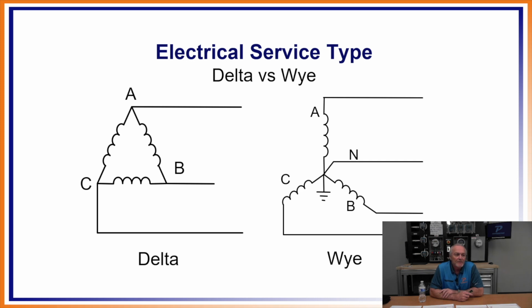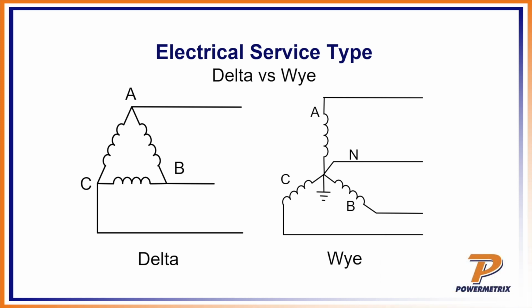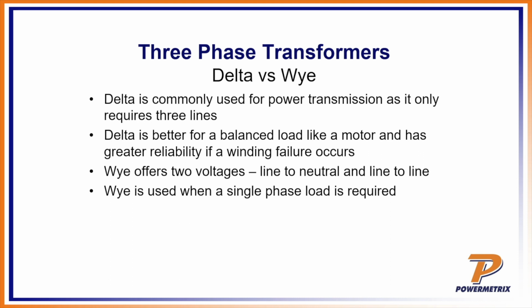So the two electrical service types that we talk about all the time are delta versus the Y, right? So delta, you'll hear guys say it's pretty easy to recognize the delta, because it's shaped like a delta, and then the Y is shaped like a Y. And you probably recognize the one on the right from Back to the Future. It looks a lot like that flux capacitor, doesn't it? The one on the right there. So 3-phase transformers, delta versus Y. Let's talk about it. The delta is commonly used for power transmission. It only requires 3 lines, right? The delta is better for balanced load like a motor and has greater reliability if a winding failure occurs.